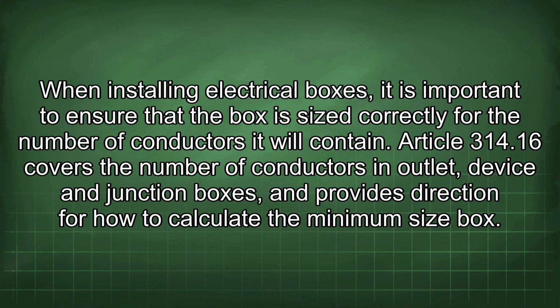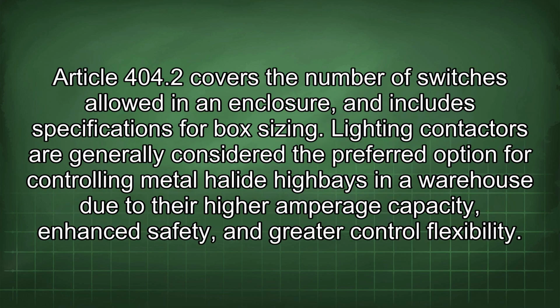When installing electrical boxes, it is important to ensure that the box is sized correctly for the number of conductors it will contain. Article 314.16 covers the number of conductors in outlet, device, and junction boxes, and provides direction for how to calculate the minimum size box. Article 404.2 covers the number of switches allowed in an enclosure, and includes specifications for box sizing.